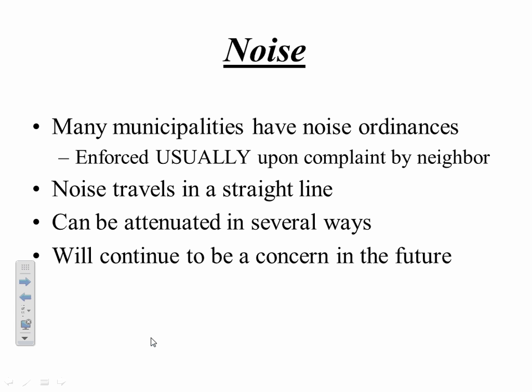Other things that we've been talking about in some of the sound attenuation housing designs are noise. I'll give you a little bit more to look at here. Many municipalities have noise ordinances, and to date they've been putting them on their websites. You might have to call and find out where exactly they put them. They put them in different places, but one thing about noise ordinances, they're usually enforced only when there's a complaint. Then they'll drag the book out and see how high it is, and noise travels in a straight line. It can be attenuated in several ways. We've looked at a couple different designs. We know that if we can turn the noise, it quiets it and attenuates it. And it will continue to be a concern in the future, as long as we have an EPA.